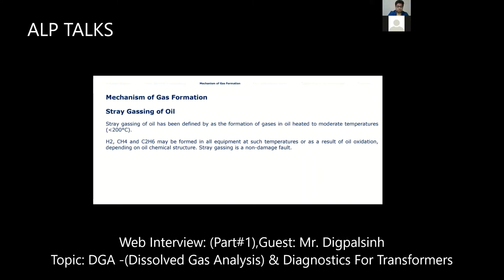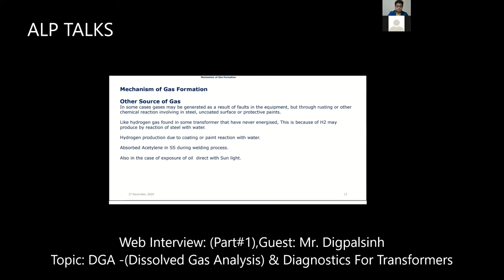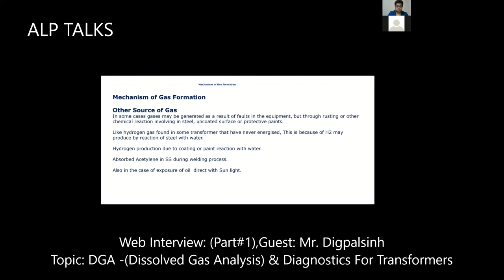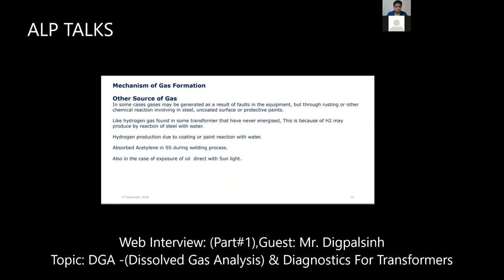It is produced by chemical reaction with the top yoke or some steel material. The protective paint that we apply to the top yoke, the bottom yoke, and every steel part, if this paint is damaged, then hydrogen is also produced just by chemical reaction between the steel and the oil, at some minor temperature. Not minor, beyond 100 degrees Celsius. Then, in the mechanism of gas formation, other sources of gas are rusting of the steel parts, chemical reaction at uncoated steel surfaces, or, as I already said, damage of the protective paint.